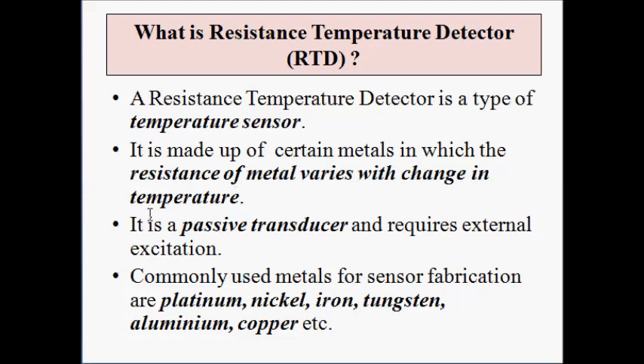RTDs are passive transducers. It means they require an external voltage supply for their operation. They are not self-generating and cannot generate their own voltage. They only respond by a change in resistance. That change in resistance is converted into a change in voltage with the help of an external voltage supply and a signal conditioning circuit.